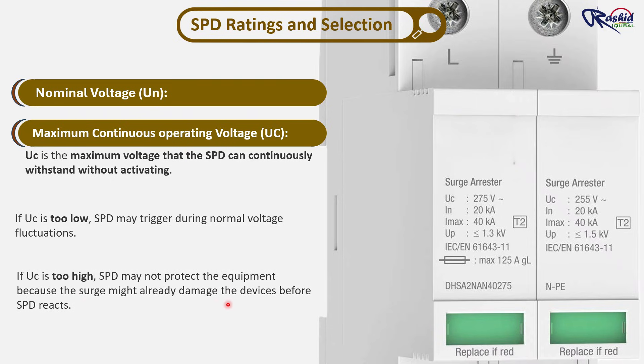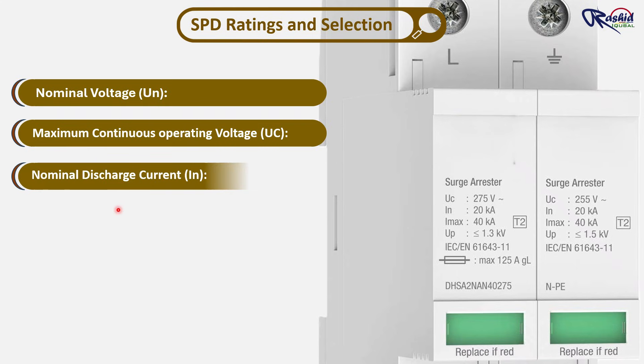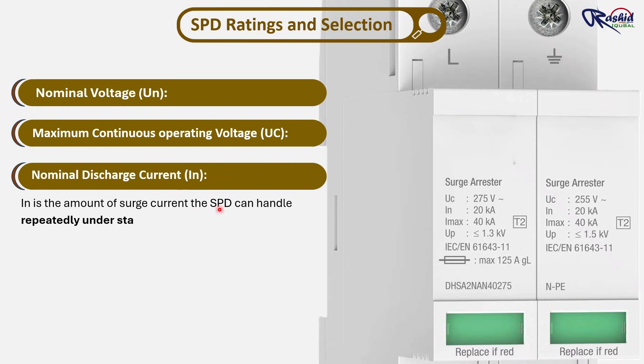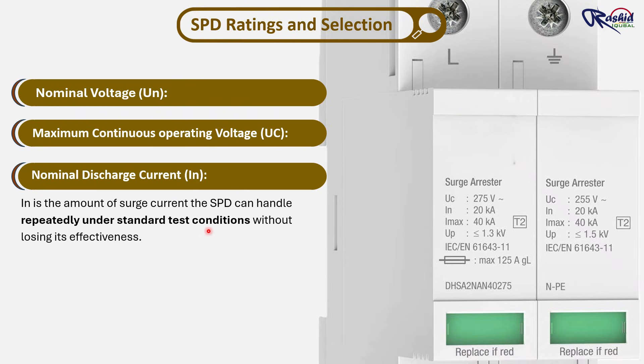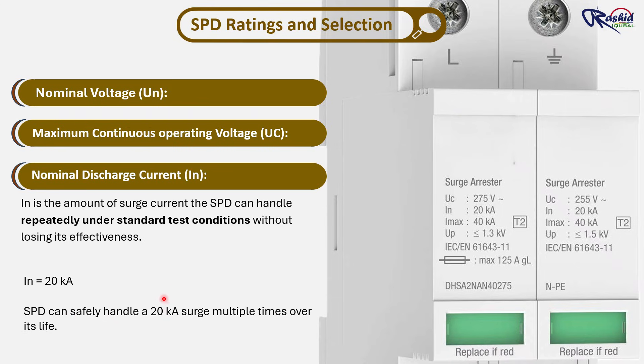Number 3 is nominal discharge current, IN. IN is the amount of surge current the SPD can handle repeatedly under standard test conditions without losing its effectiveness. For example, if the IN rating is 20kA, then the SPD can safely handle a 20kA surge multiple times over its life. This indicates how robust the SPD is for normal surges like switching operations or small lightning surges.